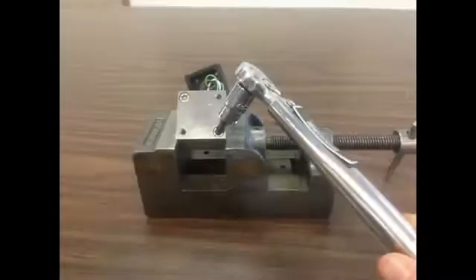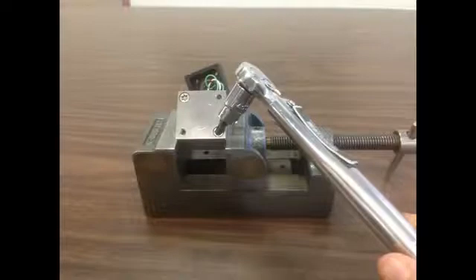Be sure to carefully tighten the body bolts to 125 inch-pounds in stages to achieve the required clamping force. If the calibration does not produce a linear output or the signal exhibits high hysteresis the diaphragm may need replacement. This will be the case if you have over-pressured the sensor to twice its differential pressure range.